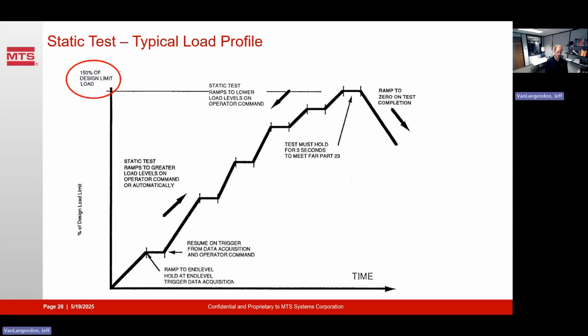In general these are slow, methodical tests. The tuning isn't super hot - you want conservative P gains when testing this. These tests may take months or years to assemble, but each test case is typically only a matter of minutes or hours, so they'll run multiple test cases. As you can see here, it's a slow, steady, graduated increase, typically in 5 or 10% increments, as you work your way up to the ultimate load.